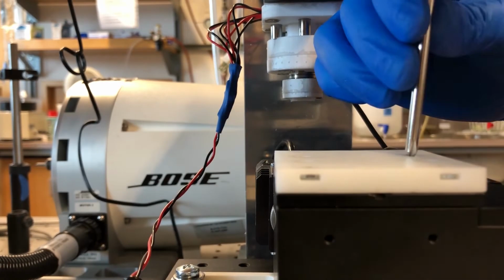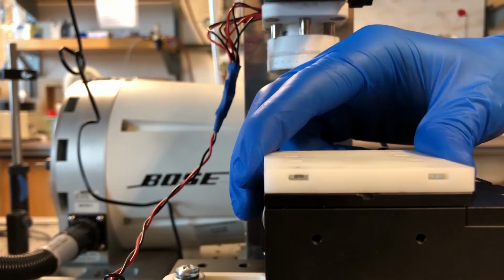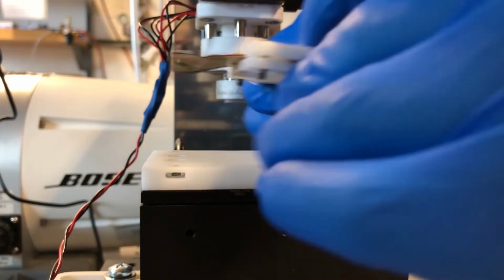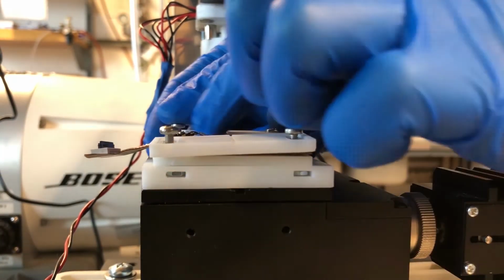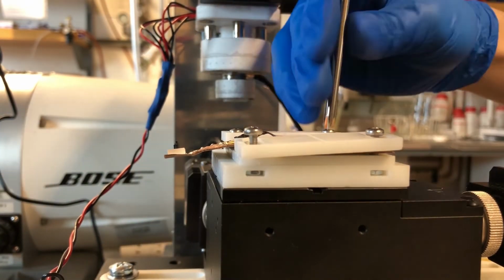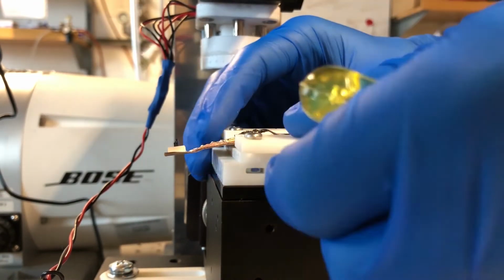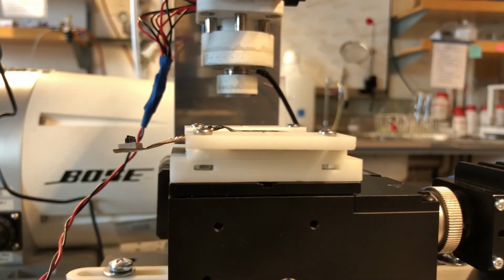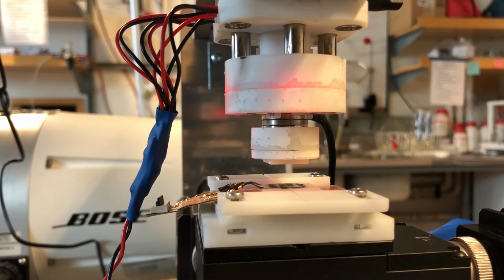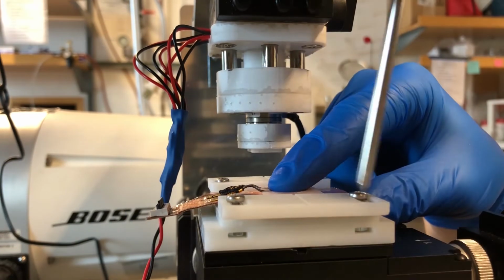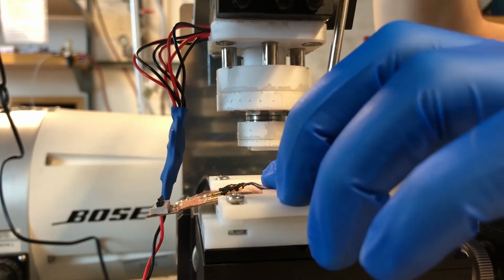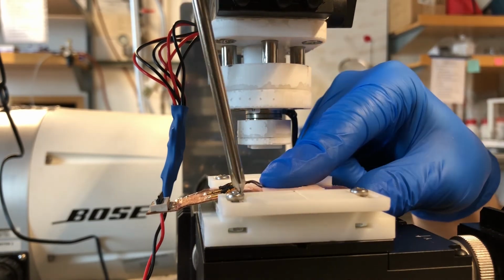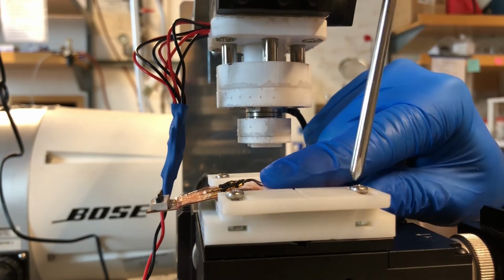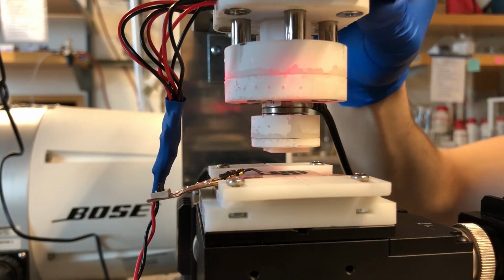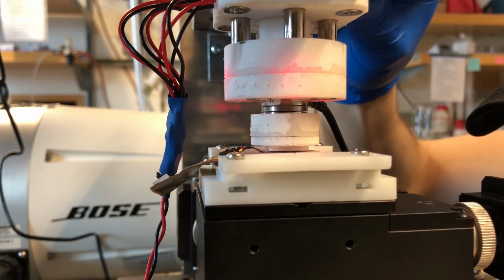The next step is mounting and aligning the sensor. First, place the piece that mounts to the stage. The max load force on the stage is 10 newtons. Make sure to be careful. Gently mount the sensor with the clamps. Do not fully tighten the sensor until we are ready to align. Apply light pressure to ensure the sensor is properly secured to the surface. Align the sensor as best as possible using the lasers and your vision.